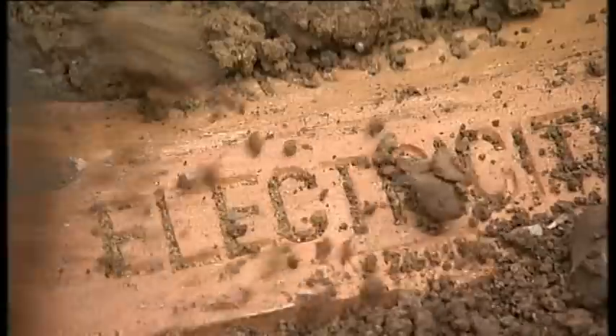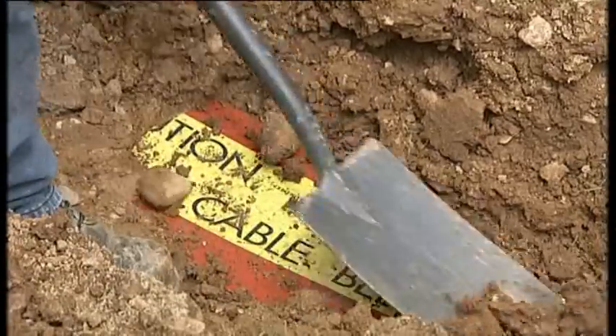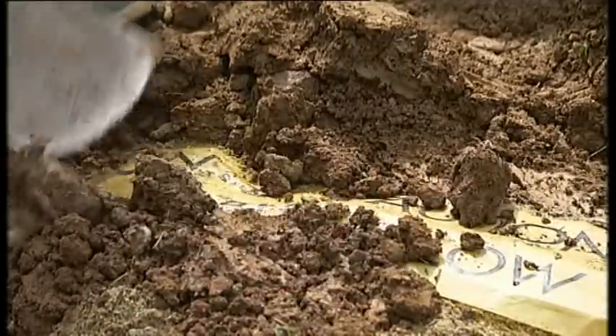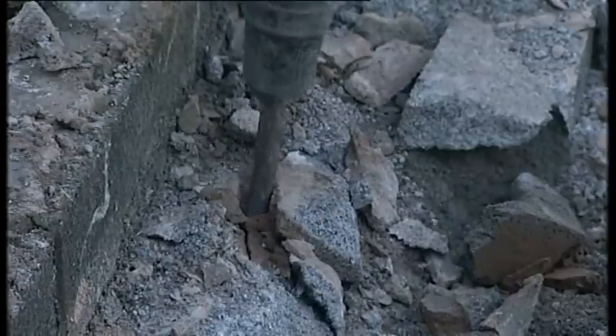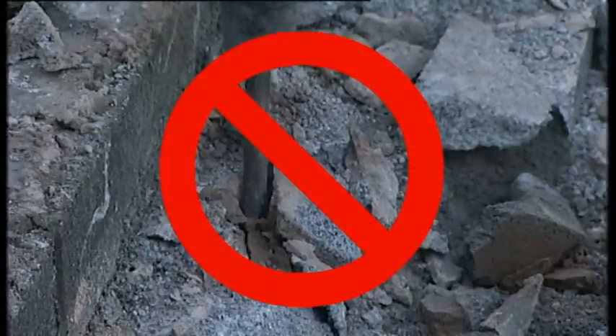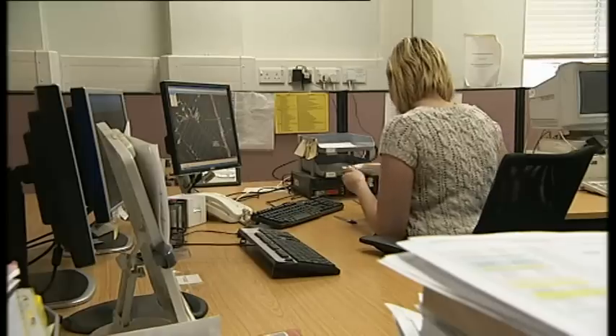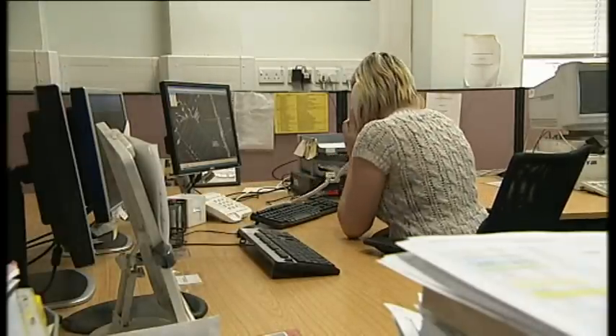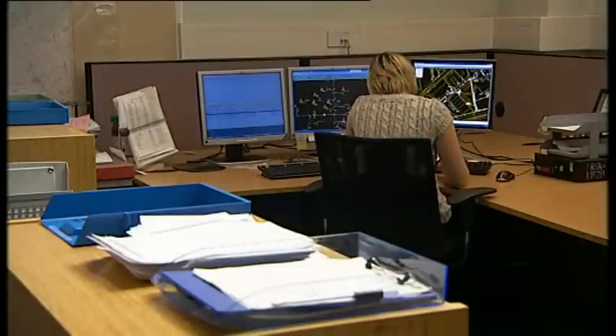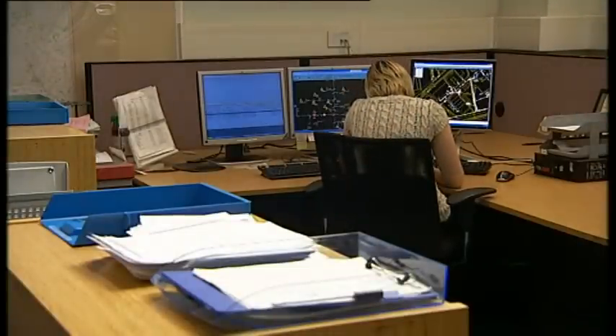Once you get near to the cable, there should be tape or tile covers like these, but they might have been removed, so please don't rely on them to warn you. If you come across concrete around our cable, there's no safe way to break this out while the cable is live, so route your excavation elsewhere if you can. If you can't, contact us immediately. And please don't ever concrete in our equipment. You'll just be creating a dangerous situation for somebody else in the future.